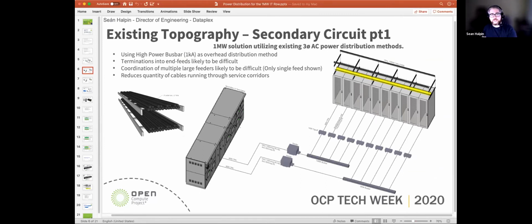Realistically we have two main options that haven't changed. One is to go with overhead bus bar, albeit not the same type of bus bar we generally use at the moment in a data center. There are some high amperage options available, but in my mind I'd see this as an encapsulated bus bar, similar to a rising bus bar system you'd have in a hotel or hospital, with very large tap-offs. If you want to flick to the next one, Gabi.